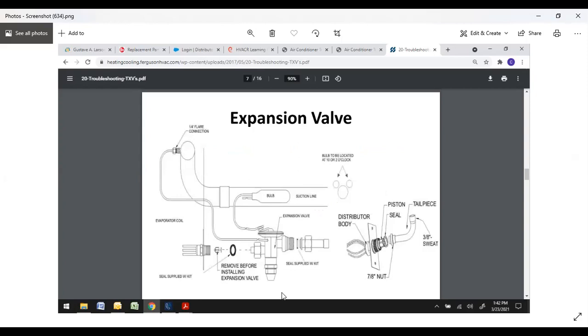So this is going to be your typical Rheem expansion valve right here, your bulb, suction line. This is important if you ever have to replace one. With the Rheem, you only have your two screw-on fittings here, so you don't have to worry about a torch. So you've got your small connector here, you got your two lines here. You will have two O-rings coming out each side of here. Make sure you remove the old O-ring and install the new O-ring in each side. If you don't, it will leak. It doesn't matter how tight you get it, it will leak. So make sure that your O-rings are in there.